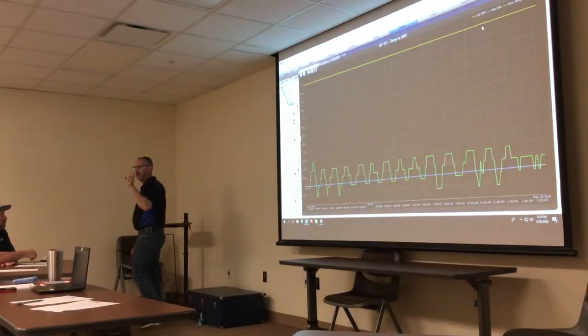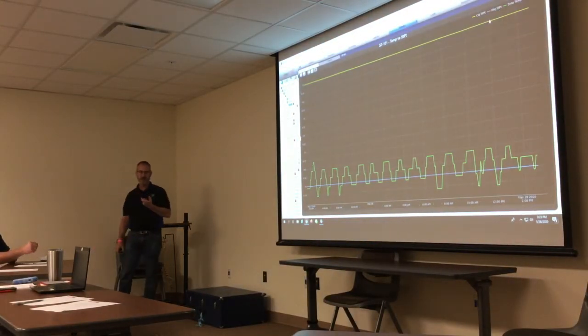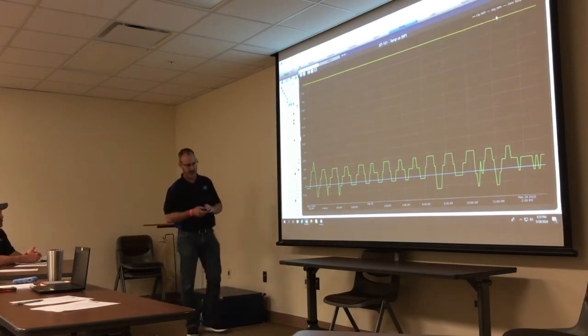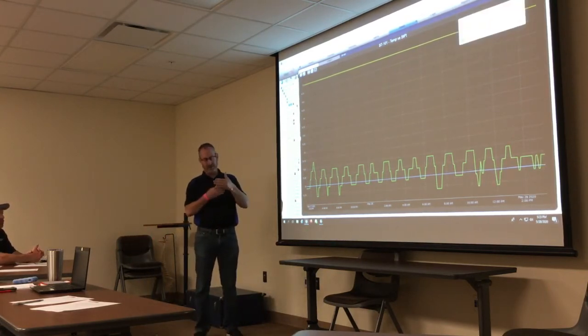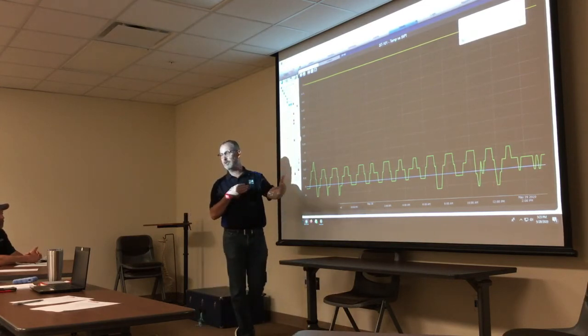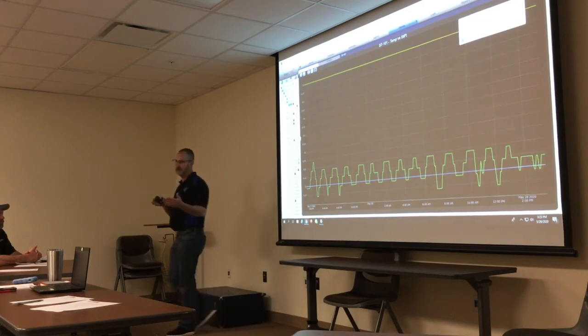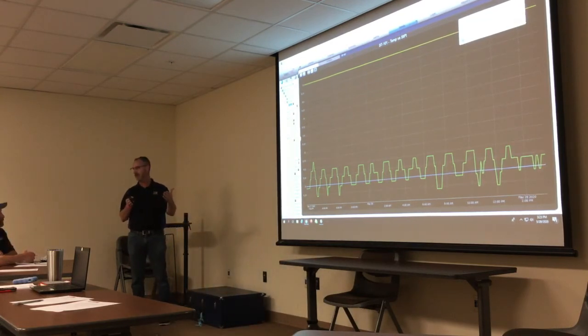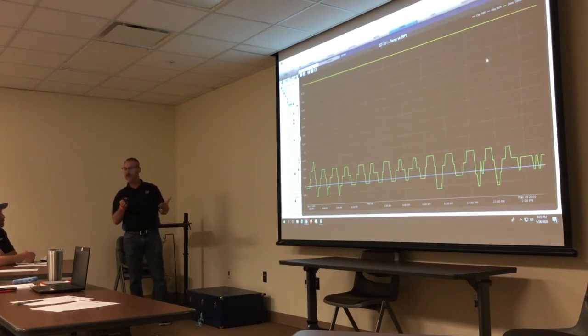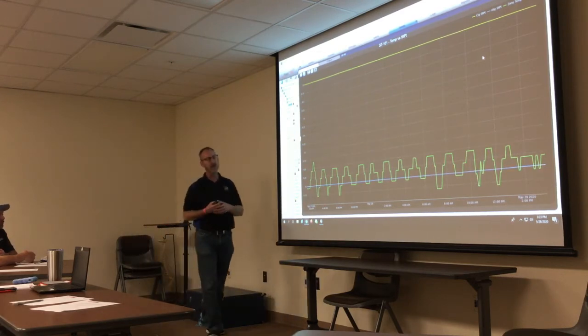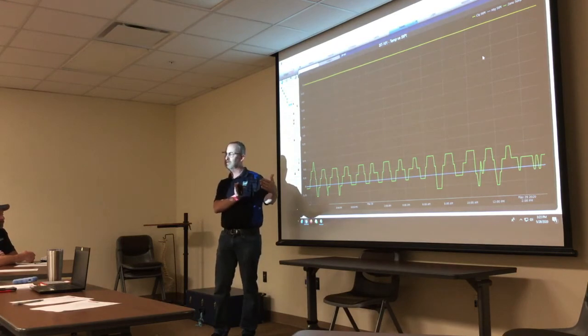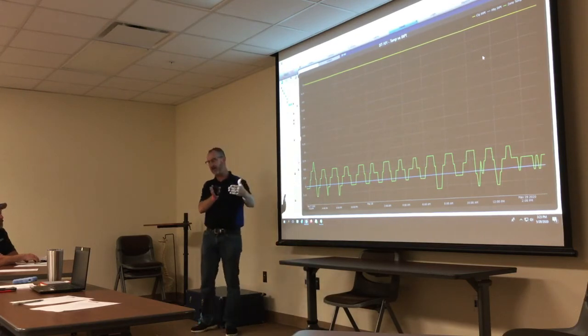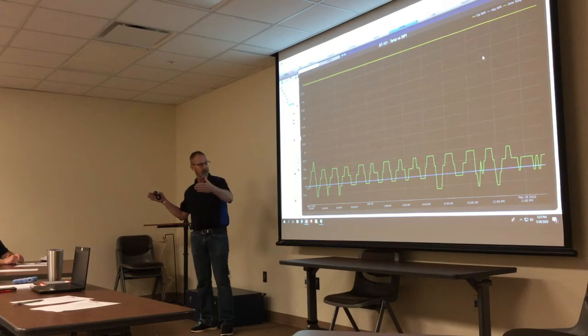The controller stores 24 hours worth of trends - that's all that's on board in a controller. So if you lose communication or something, that controller will continue to run, continue to do its job, and even store trends, but it has memory small enough that it can't store everything. As soon as it regains communication, it'll push those trends back to the server. If we view the ones in the controller, there's probably about half a day's worth of trends that haven't been stored to the server yet. So if we view that in database only mode, we're only going to see from 4 o'clock this morning until back into the future.